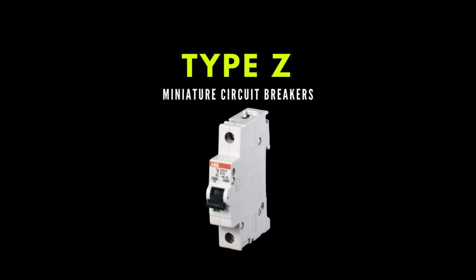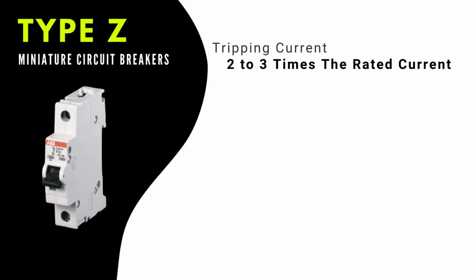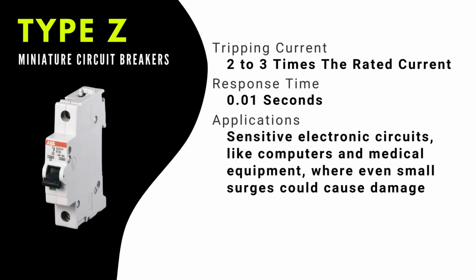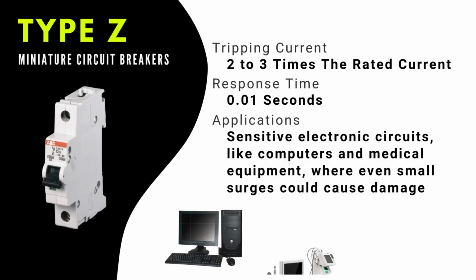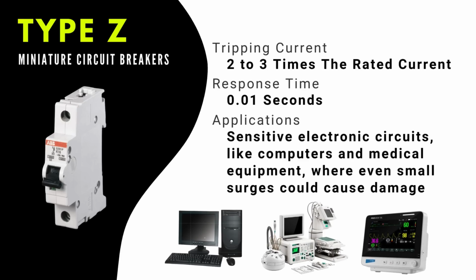Finally, we have the Type Z MCB, which is also highly sensitive, tripping at just 2 to 3 times the rated current. These MCBs react very quickly, with a tripping time of less than 0.01 seconds. Type Z is often used to protect sensitive electronic circuits, like computers and medical equipment, where even small surges could cause damage.